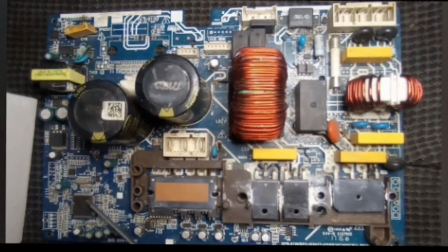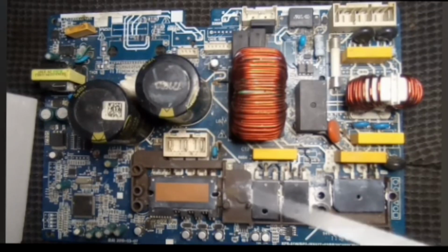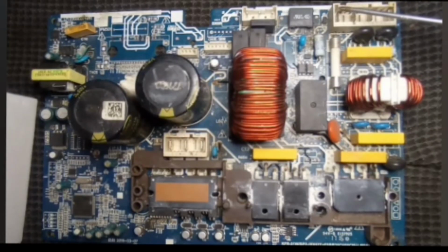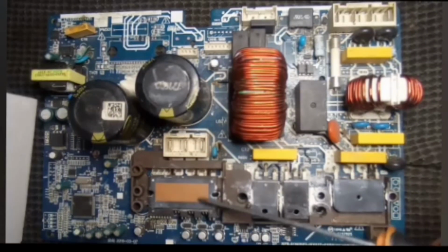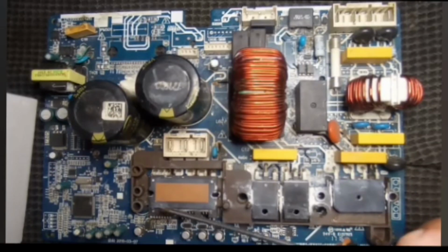This is very important because electrical noise can affect both the microprocessor as well as all other electronic components or the board sensors. That is why it is so important to be able to divert those electronic noises through the grounding in inverter air conditioners. In addition, significant amounts of electrical noise can damage the IPM and even also the compressor.